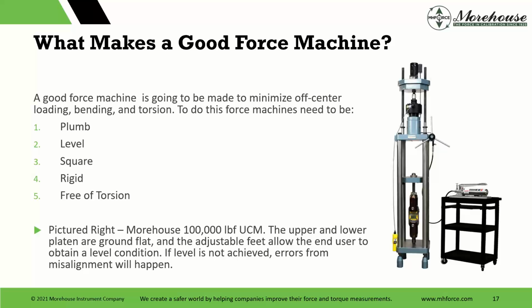Here pictured right, we have a 100K UCM. The upper and lower platen are ground flat, and adjustable feet allow the end user to obtain a level condition. If level is not achieved, errors from misalignment will happen. So really important, those feet, they look pretty generic to me sometimes, but it's really important to get everything leveled as straight as possible because it will make your calibrations as good as possible.